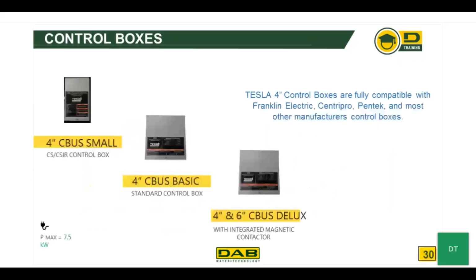In this section, we're going to talk about control boxes that are used for the 4-inch motors, specifically the GG line of 4-inch motors. The TW line does not require a control box because it has an internal capacitor. The DAB line or Tesla line of control boxes contains 3 main control boxes. This is the 4-inch CBUS small for up to 1 horsepower motors, the 4-inch CBUS basic for up to 5 horsepower motors, and then there is the 4-inch CBUS deluxe for up to 5 horsepower motors.